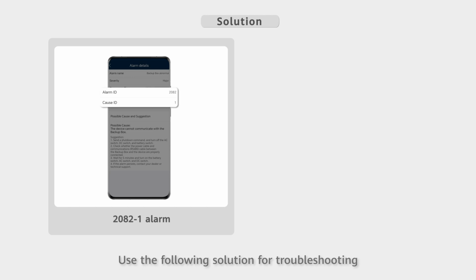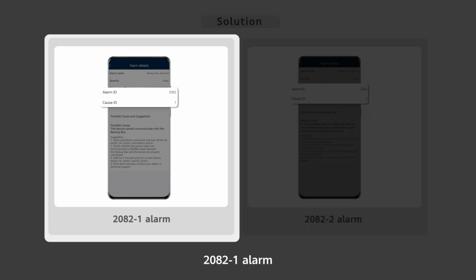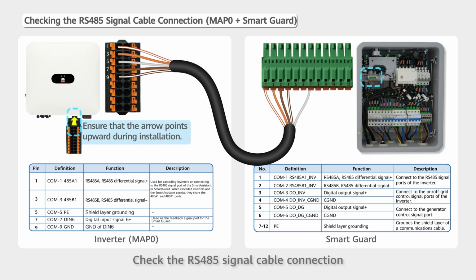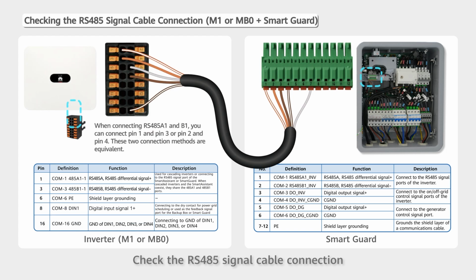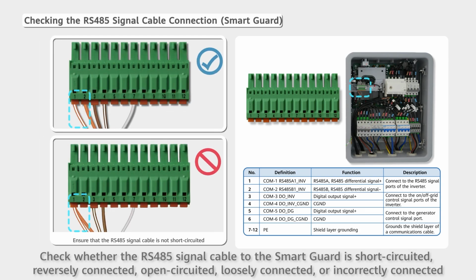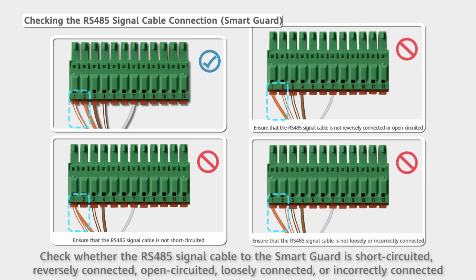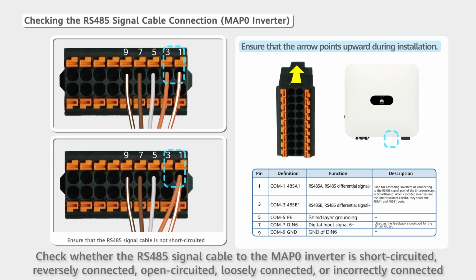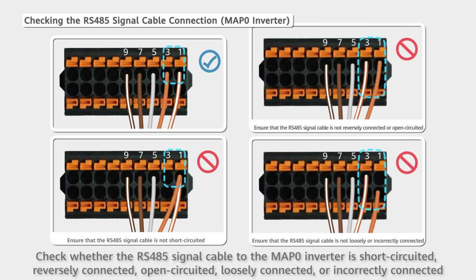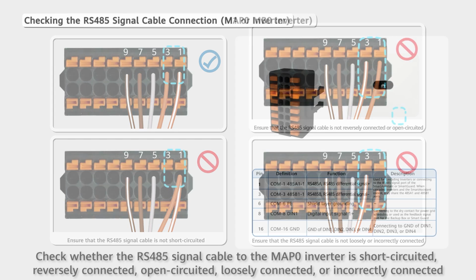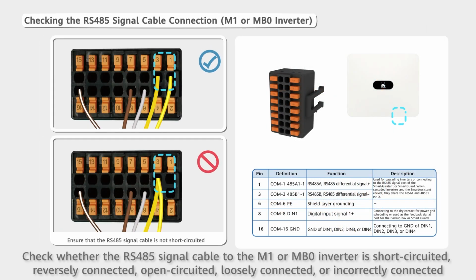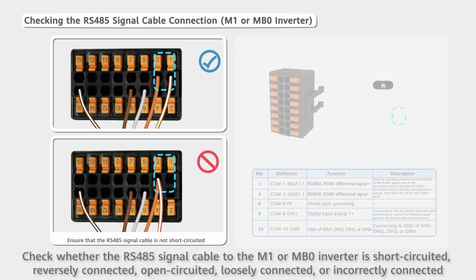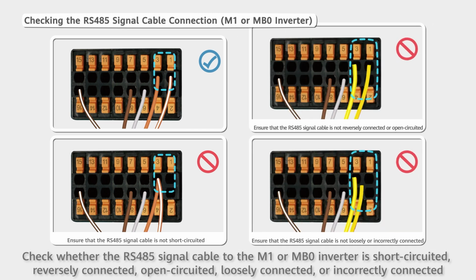Use the following solution for troubleshooting. 2082-1 alarm. Check the RS485 signal cable connection. Check whether the RS485 signal cable to the smart guard is short-circuited, reversely connected, open-circuited, loosely connected, or incorrectly connected. Check whether the RS485 signal cable to the MAP0 inverter is short-circuited, reversely connected, open-circuited, loosely connected, or incorrectly connected. Check whether the RS485 signal cable to the M1 or MB0 inverter is short-circuited, reversely connected, open-circuited, loosely connected, or incorrectly connected.